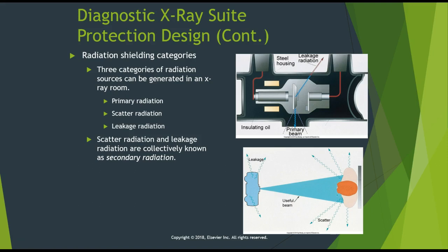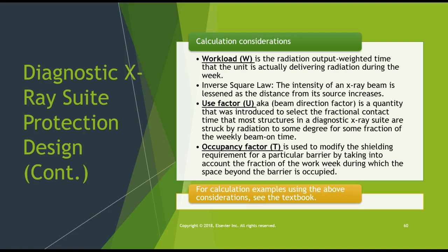Okay, the shielding categories that they are shielding for are the primary beam and then the secondary, which is going to be scatter and leakage radiation. Okay, the calculation considerations that they take into mind when they're building an imaging suite are the workload. Workload is designated by a W, and it is the radiation output. It's the time the unit's actually on. So when that X-ray tube is energized, that is the workload, and it is usually designated in units such as milliamperage per minute per week.